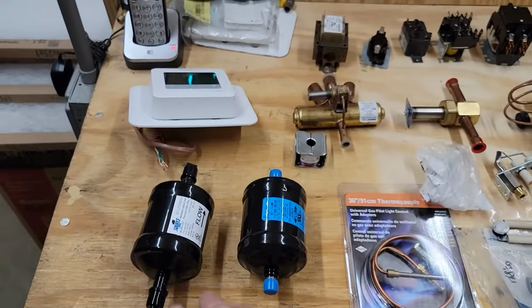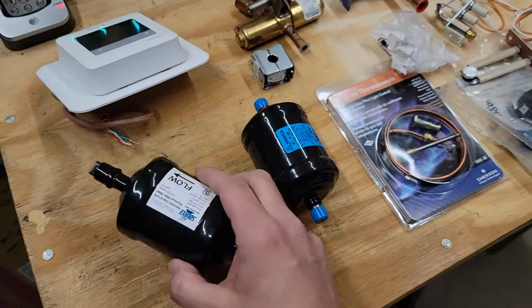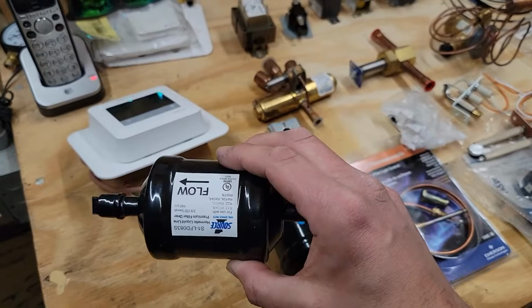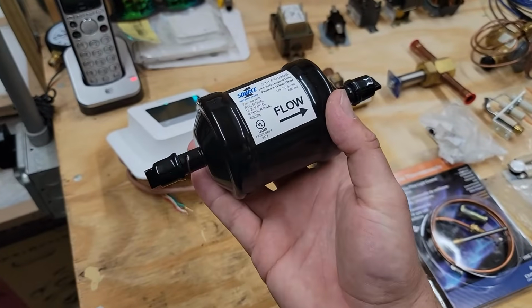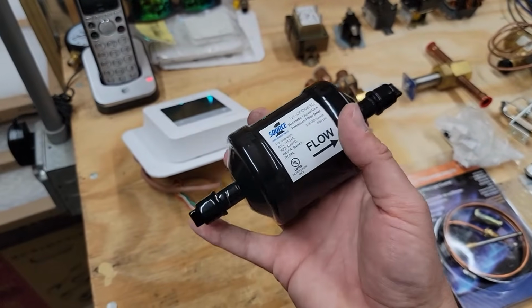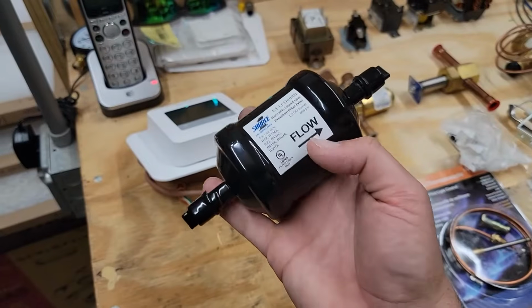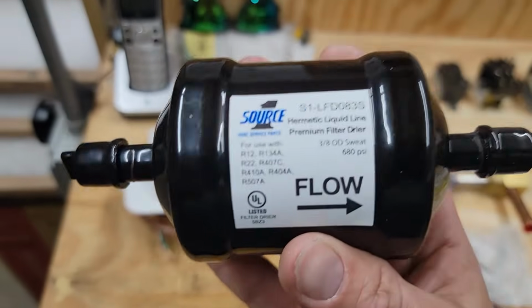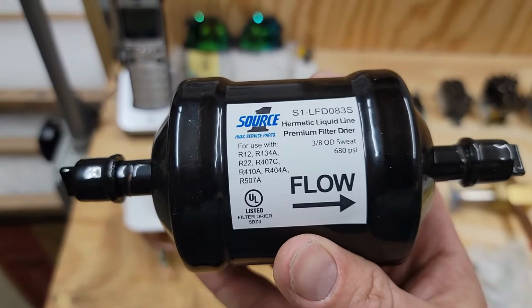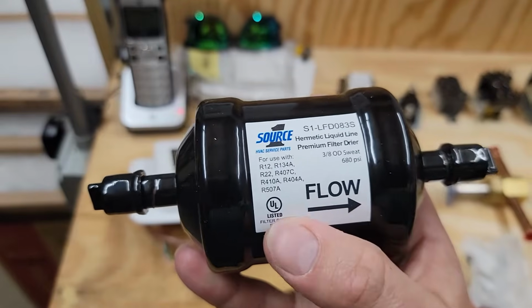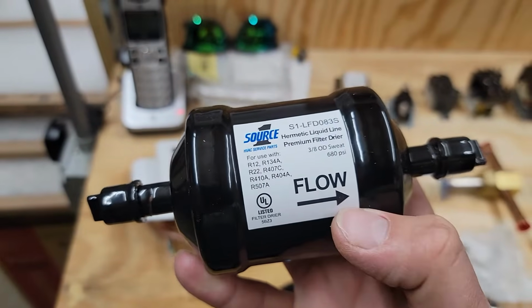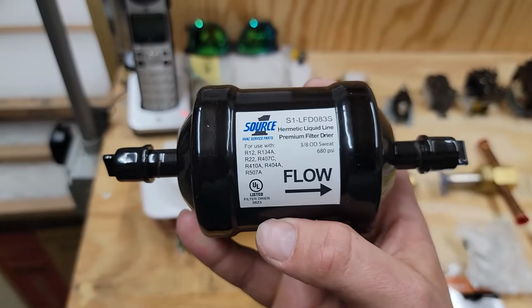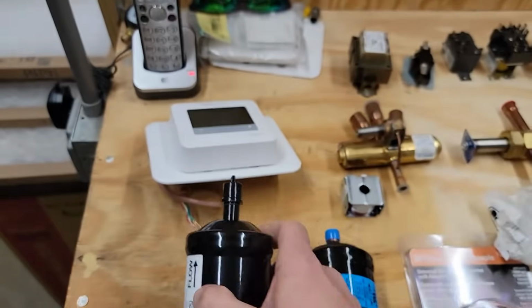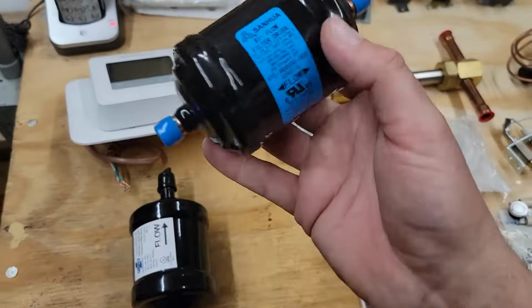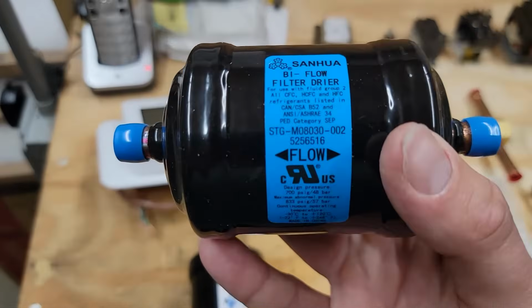So from left to right, let's go over filter dryers first. A filter dryer is a filter that is installed in the refrigeration system. This one's got a 3/8 connection, so 3/8 copper would go to this, and this is a single direction flow filter dryer. So the flow of the refrigerant will only go in one direction, so you would not install this on a heat pump, because of course we would install a biflow filter dryer for a heat pump. So this is a biflow.